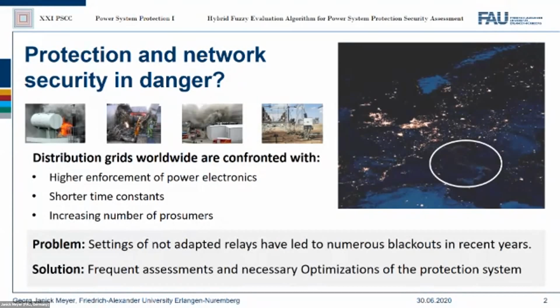Especially protection relays are disregarded in these times, even though incorrect settings of not adapted relays have led to numerous major events in the last 2 decades. Just to name the most important ones, we got, for example, the USA-Canada blackout and also the Italian blackout in 2003. The European system separation in 2006, India blackout 2012, Turkey blackout 2015, South Australia blackout 2016, Brazil major load shedding event 2018, and so on. Even if we haven't had any major event in 2020 so far, the year is not over yet.